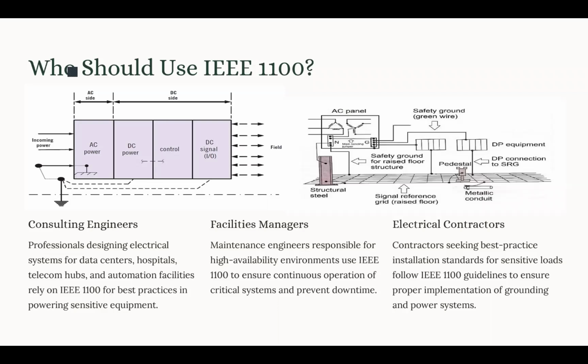Now, a design failure can lead to data loss, production downtime, or even life-threatening failures when we talk about medical systems. So basically, this IEEE 1100 is very important and essential for consulting engineers, so they can design the verification checklist for those sensitive electronic equipment based on the criteria defined in the standard.